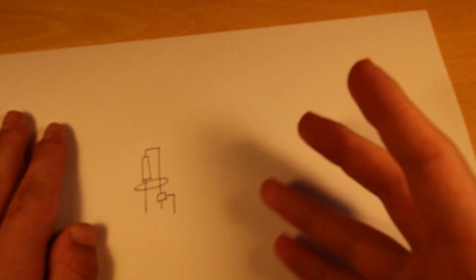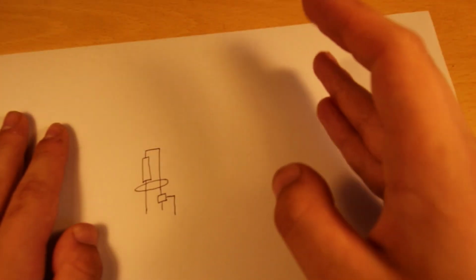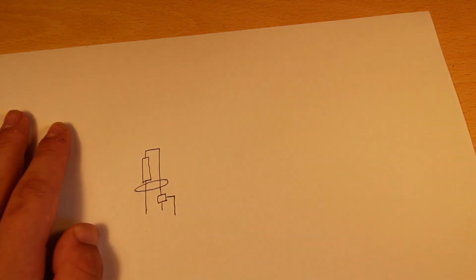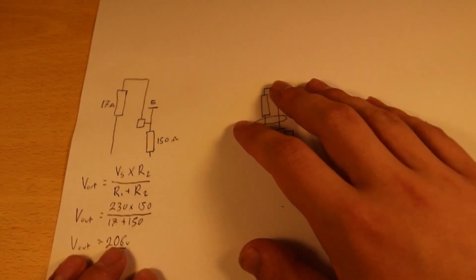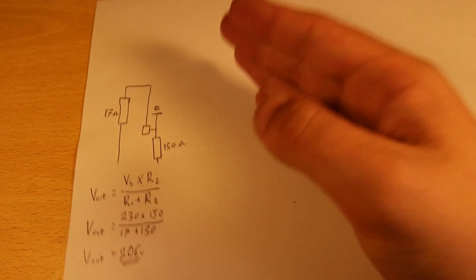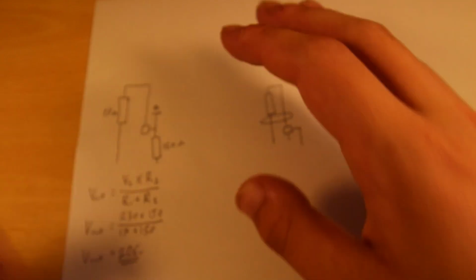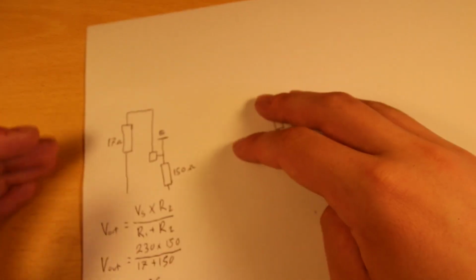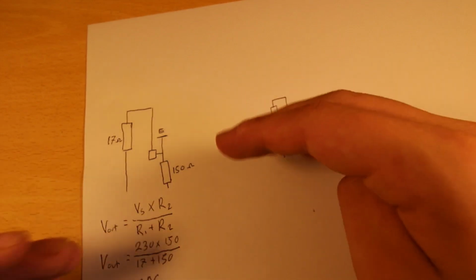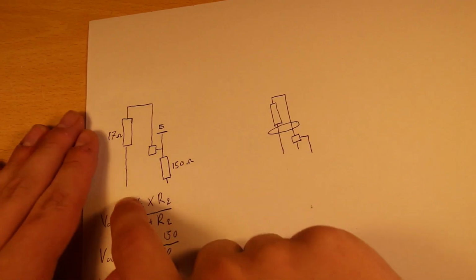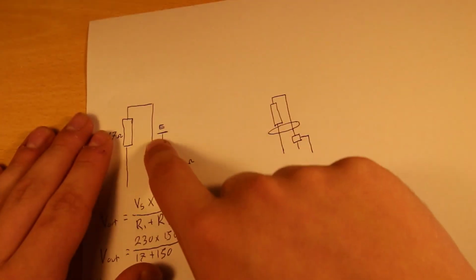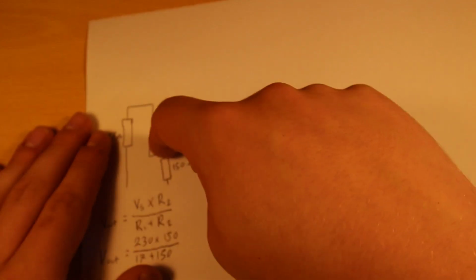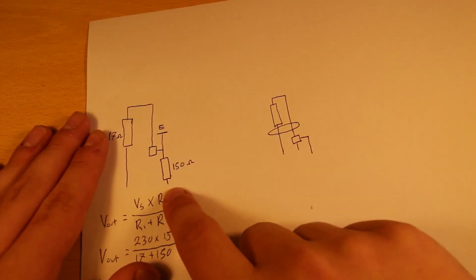The other thing people will be going is, oh well, if you put an earth rod on the earth connected to the main earth terminal, that will fix it, because all the current will then go down the earth rod to earth and you'll get no dangerous voltages. But again, that's not true because of this here. The earth rod will have an impedance, 150 ohms is about average. It can often be much higher than that, sometimes it's lower, it depends on the conditions at the time. But we will say, for example, a 17 ohm kettle heating element, that will be passing 13 amps. If we look at the path the current will take, it will go up the live, through the kettle element, back down the neutral, it will come into the service head, through that link, and then try to go down to earth through your earth rod.